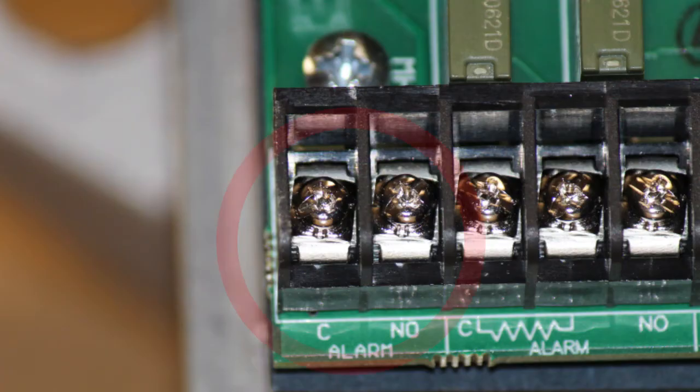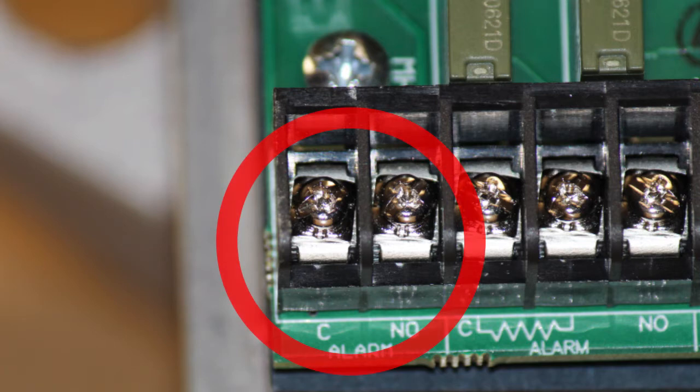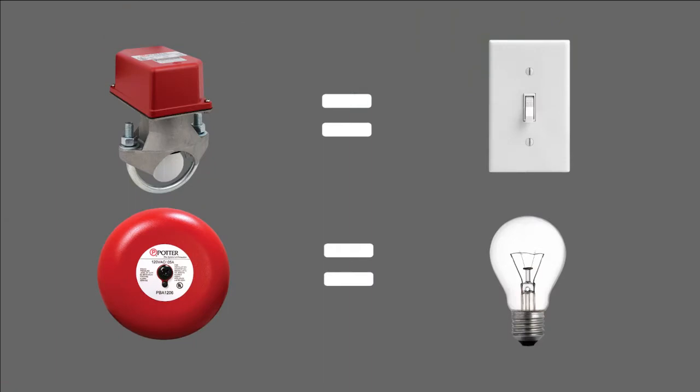The last two terminals on the left are a set of normally open dry contacts. These will typically be used to operate a local bell. These are just open switch contacts, do not connect power directly to them. They can be used to switch power through them to operate a bell just like a light switch is used to switch power to a light.